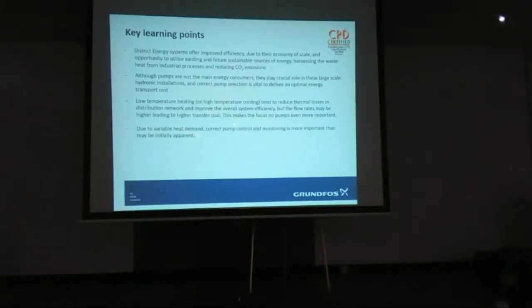Variable heat demand, that control is essential. Get that right. If you monitor it, you can do that quite easily. You can either do it via your BMS, or some manufacturers have their own controllers to do it themselves, and then can feed that information back to the BMS. Some manufacturers are looking at cloud-based monitoring systems, as we are. We're sort of pioneering that at the moment. So that if you wanted to look at your stuff from home, you can change. In theory, I could change our booster setting in the factory, log on, pull the data on there, and change all the duty and the parameters, and even commission the booster set from the electronics from the laptop remotely, if they remember to turn it on back at the factory.